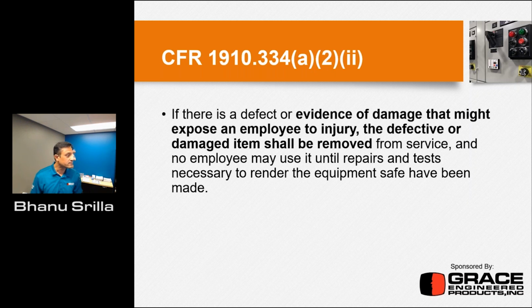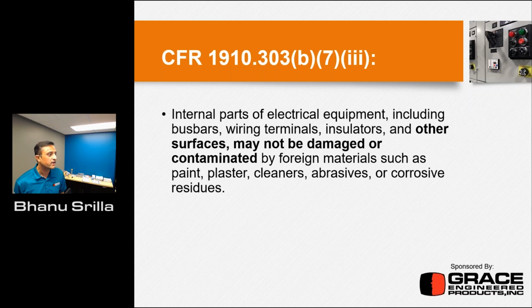And then if you look at 1910.334, if there is evidence of damage that might expose an employee to injury, the defective or damaged item shall be removed. So if the worker is performing a task, or doing an inspection around that equipment, and he comes across a red hot spot, a temperature rise, or a small arcing inside, this person has to make sure that he informs the employer and they take corrective action, so that they take this defective equipment out of service and then perform the maintenance tasks to take care of that. So then 303: internal parts of electrical equipment, including the bus bars, wiring terminals, insulators, and other surfaces, may not be damaged or contaminated.